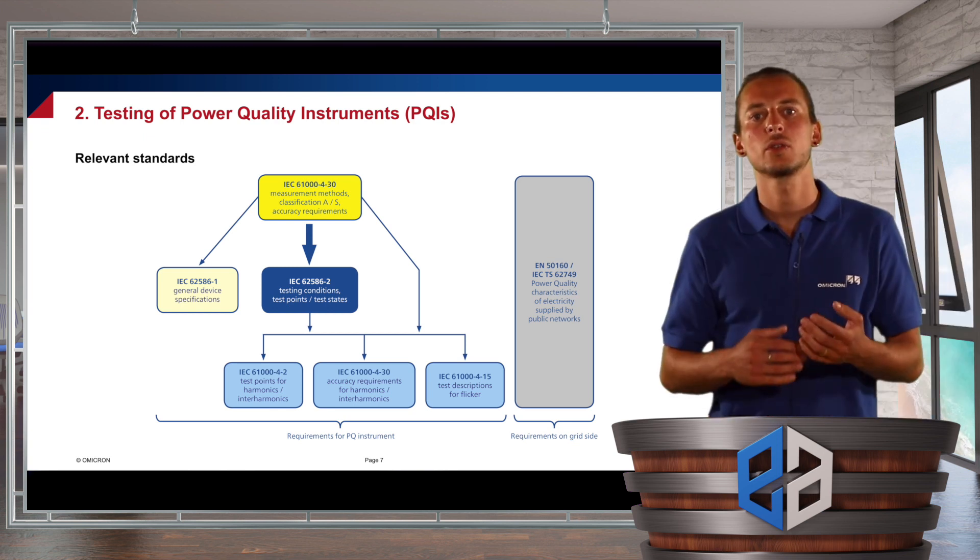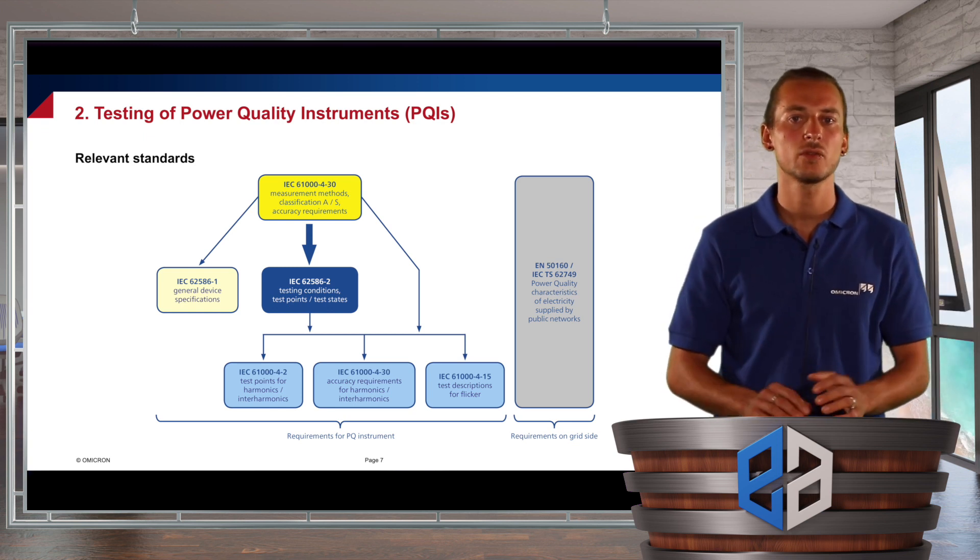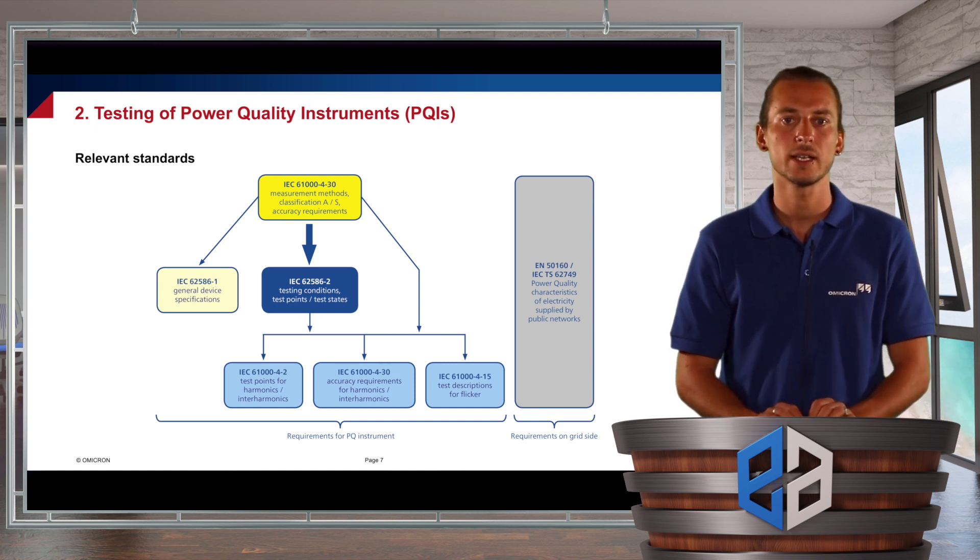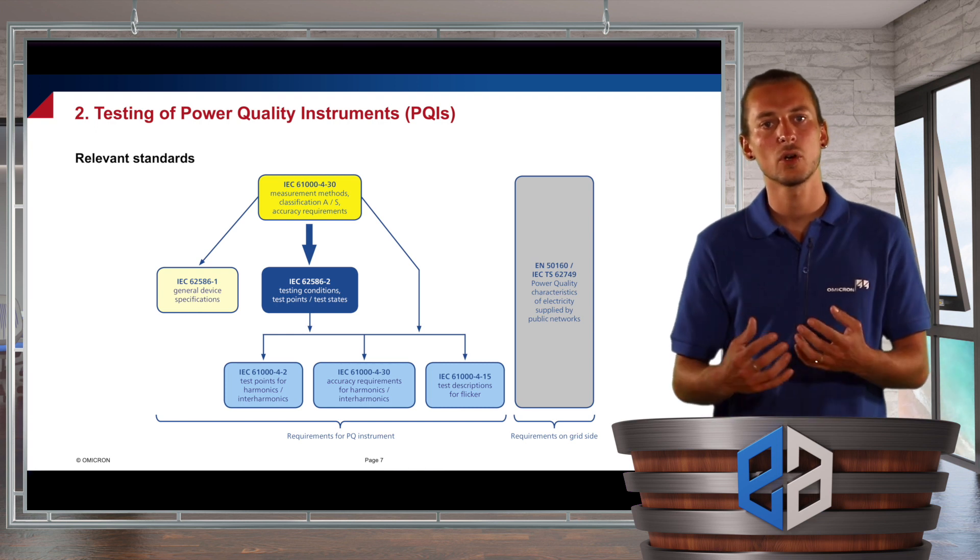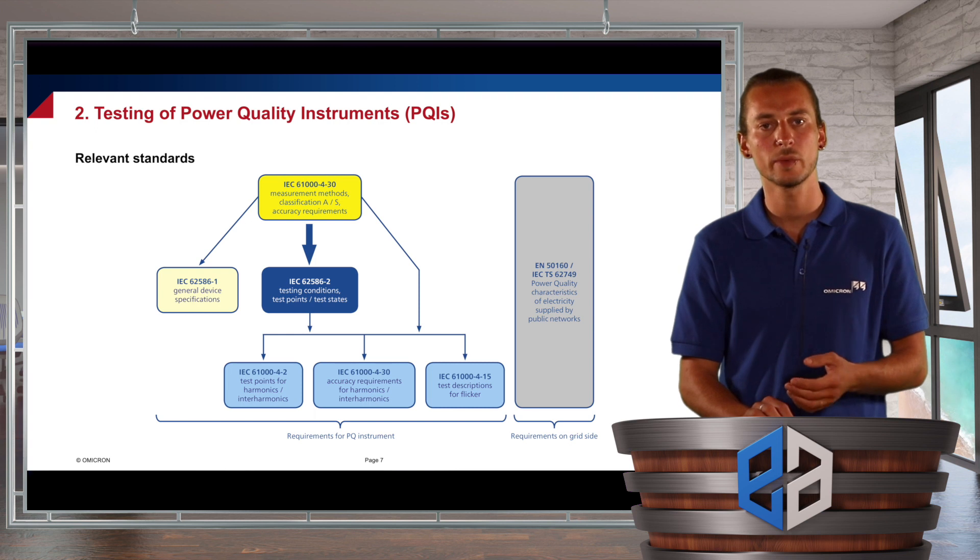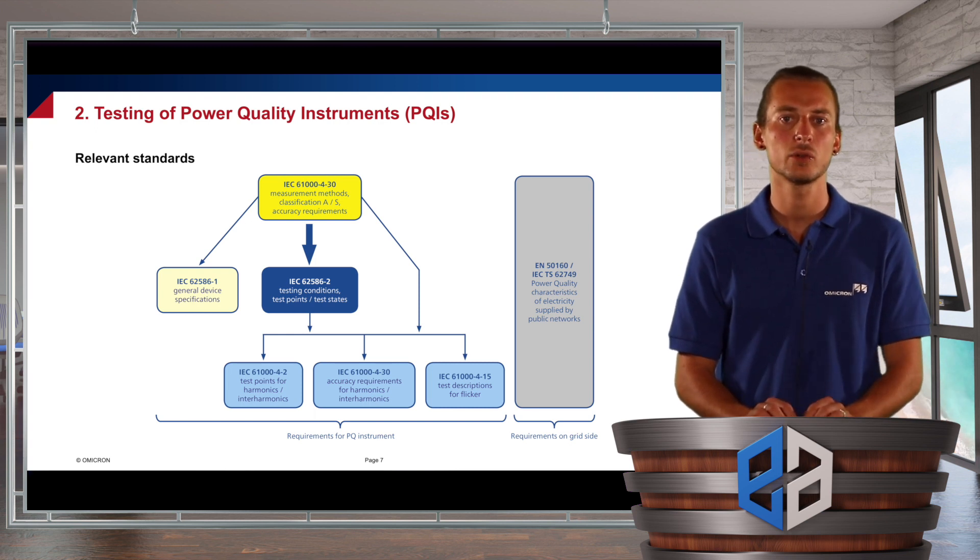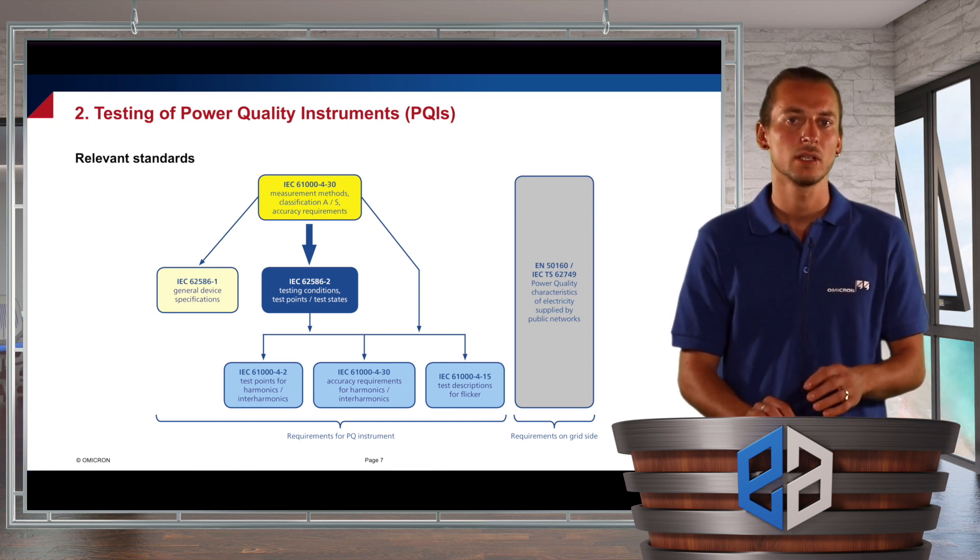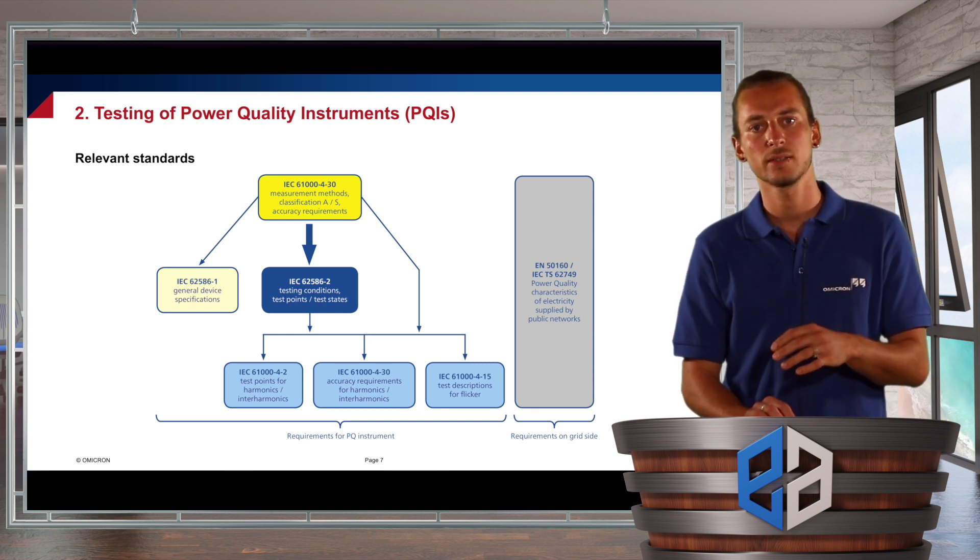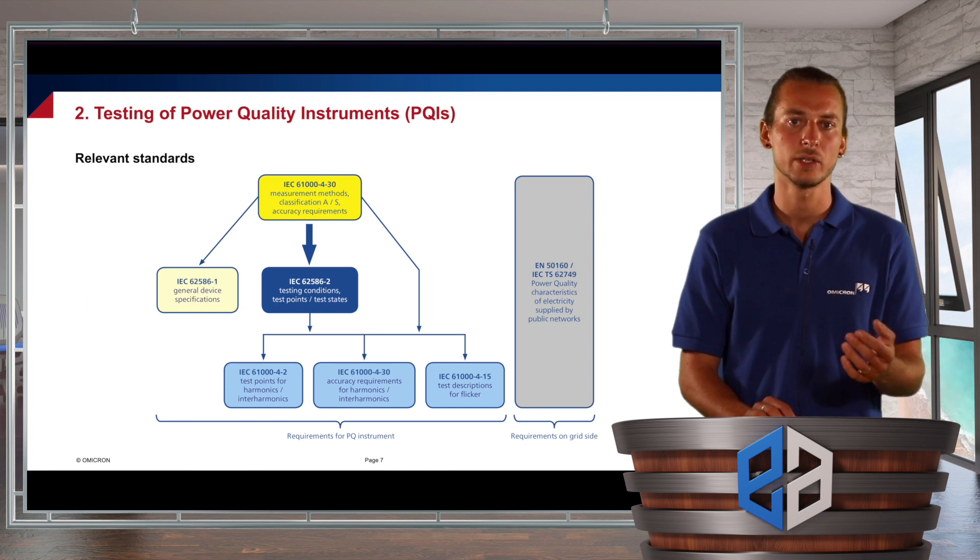So coming to the relevant standards which are valid for power quality testing. First of all, and most important, there's the IEC 61000-4-30, which is the most important standard when it comes to requirements for power quality instruments and also defines the accuracy requirements and the classification into class A, which is very accurate, or class S, which is a little bit less accurate.